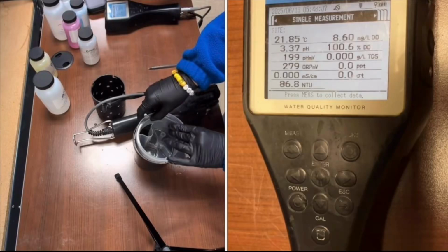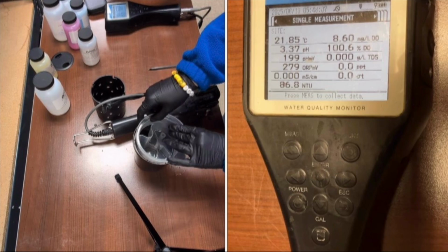All right, moving on to our last and final calibration, we will be calibrating for DO. It's important to note that for the 0-point calibration for DO, you will be calibrating for percent DO, but the number that you will be writing down on the calibration sheet is from mg/L DO. So that number that you're writing down on your calibration sheet should be 2 decimals and not just 1. That's just something to keep in mind, and that's something that I see a lot of mistakes of.